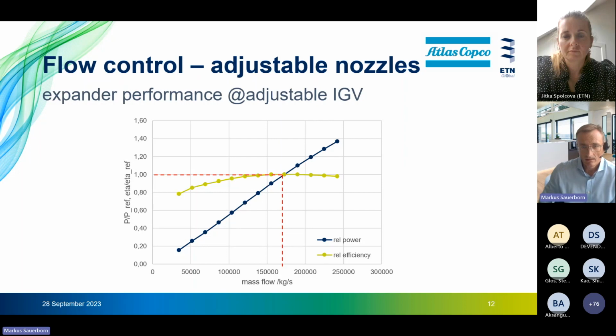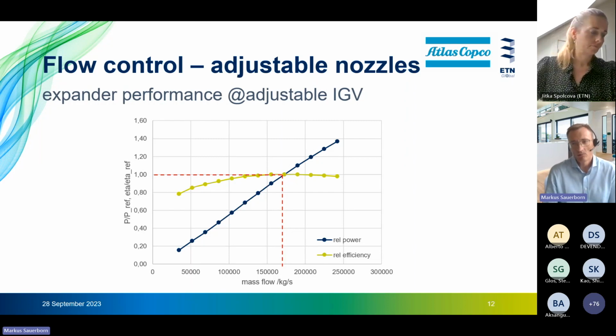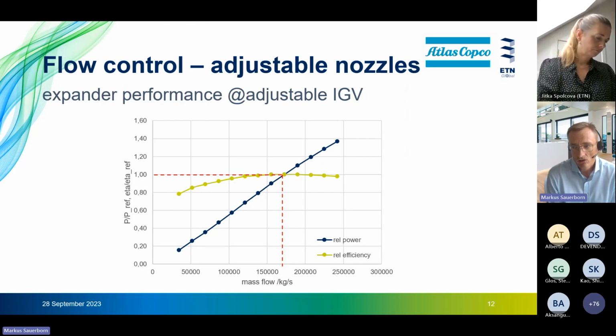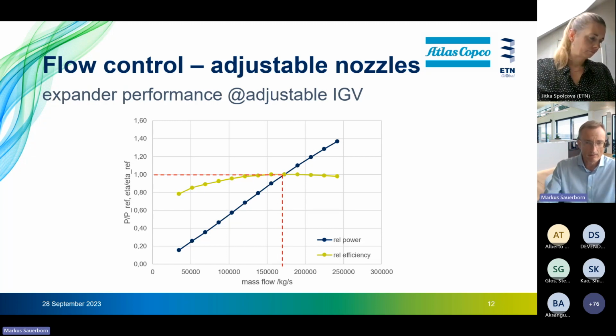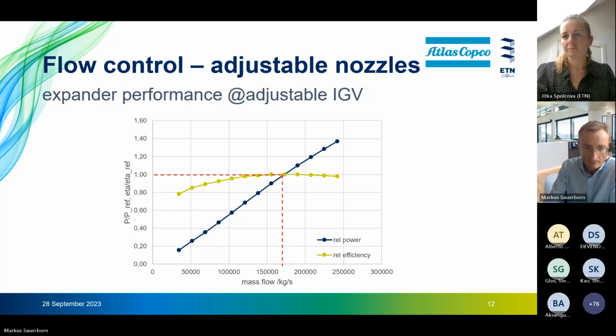But here in the next slide is shown if the process should require different flow rates. An adjustable nozzle ring design might be installed to control the flow over a wide range at stable efficiency values. And this is demonstrated in the diagram showing relative power as per the blue curve and the efficiency in green versus flow.